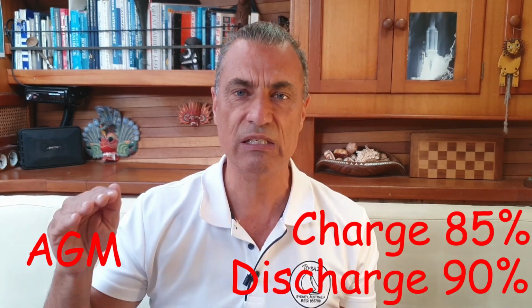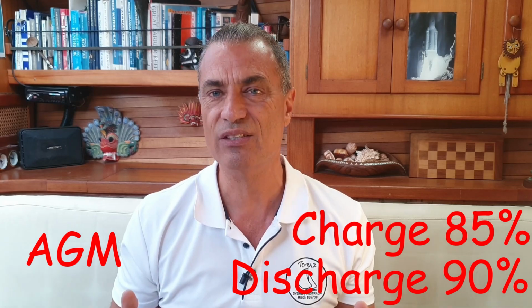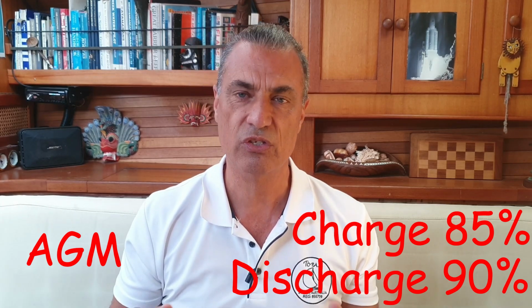For AGM batteries, the charging efficiency is slightly lower, usually around 85%, while the discharging efficiency is around 90%. But these degrade substantially as the AGM or lead acid battery ages, so you might need to adjust them every year. This monitor will give you live feedback on your battery's health, as well as historical data you can use to understand your battery's behavior over time.